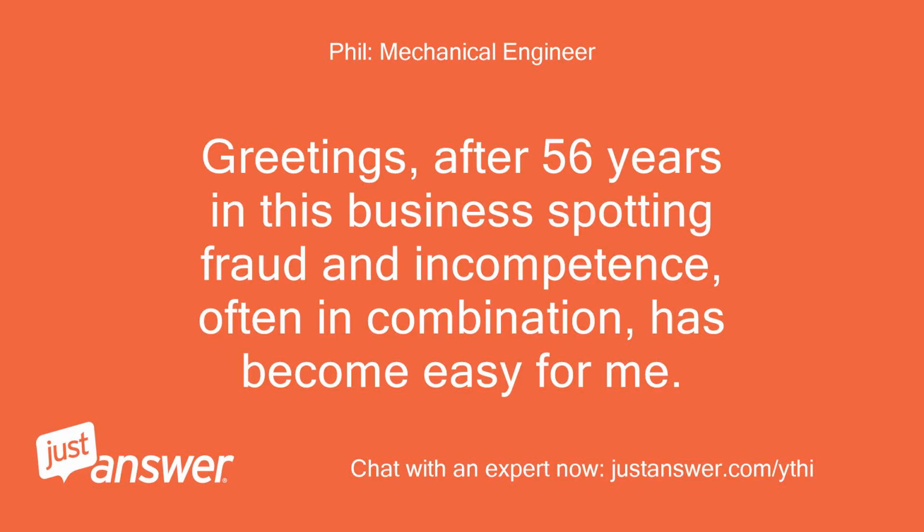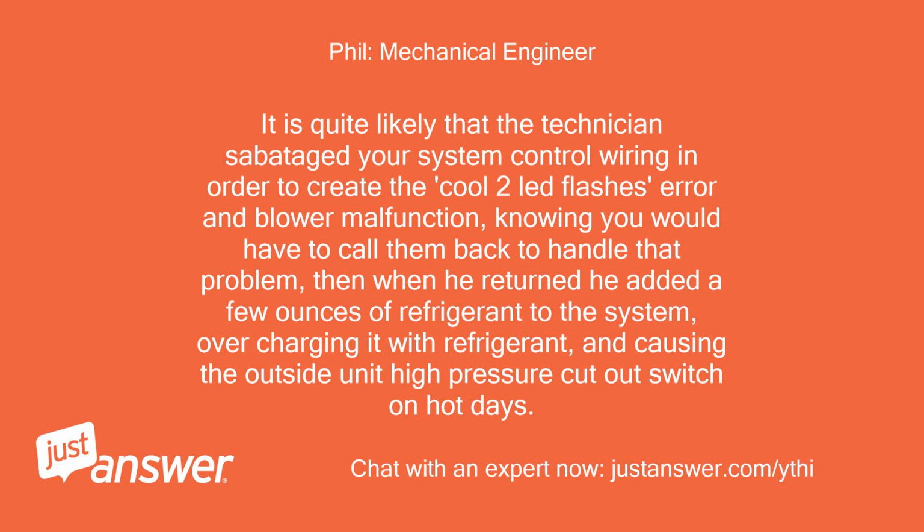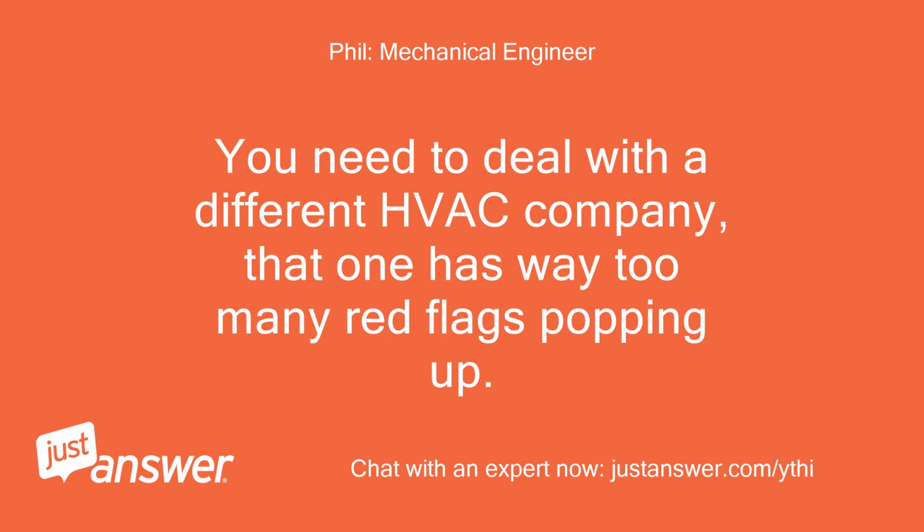Greetings. After 56 years in this business, spotting fraud and incompetence, often in combination, has become easy for me. I hardly know where to start. It is quite likely that the technician sabotaged your system control wiring in order to create the cool 2 LED flashes error and blower malfunction, knowing you would have to call them back to handle that problem. Then when he returned, he added a few ounces of refrigerant to the system, overcharging it with refrigerant, and causing the outside unit high pressure cutout switch on hot days. You need to deal with a different HVAC company. That one has way too many red flags popping up.